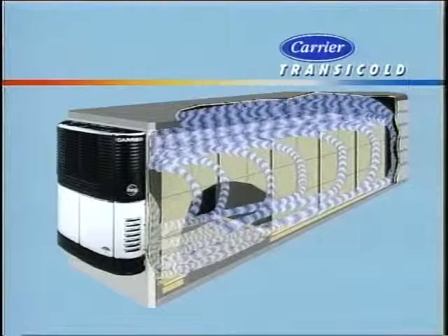The coolant recovery bottle is located behind the microprocessor side door. The coolant level should be visible in the bottle in the normal range. The radiator cap is located at the very top of the unit next to the air cleaner, on the same side of the unit as the coolant recovery bottle. Never remove the cap when the engine is hot. In most cases, you'll add coolant only to the overflow bottle.